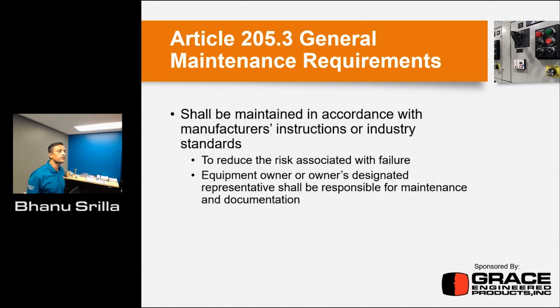So Article 205.3 talks about general maintenance requirements. It clearly calls out that it shall be maintained in accordance with manufacturer instructions or industry standards. As I previously mentioned, if you want to tie in the OSHA CFRs to this, it has to be maintained per manufacturer instructions or industry standards. So industry standards, you can use only if there is no direct manufacturer-provided guideline for that equipment, okay? And also it helps reduce the risk associated with failure. And the last bullet, the equipment owner or the owner's designated representative shall be responsible for maintenance and documentation.